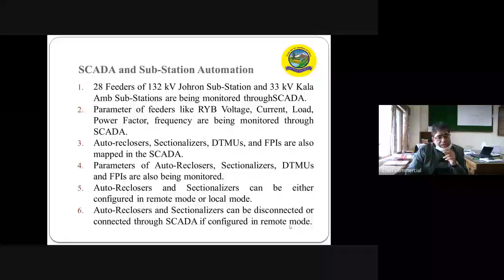Then when we talk of the SCADA system, we have 28 feeders of 132 kV substations which have been put on SCADA, and parameters such as voltage, current, load, power factor, and frequency are being monitored. These auto reclosers, sectionalizers, DTMUs, and fault passage indicators are also mapped. The parameters of auto reclosers are also being monitored, and the auto recloser can be disconnected through SCADA. We have the facility from our control room to connect and disconnect all field devices. This SCADA screen looks like this.